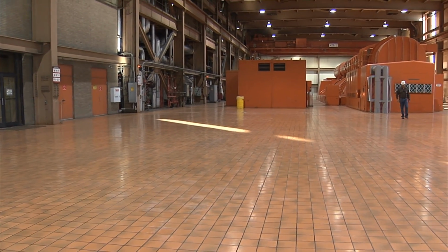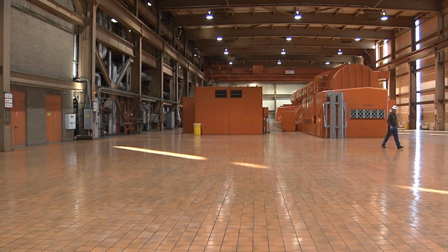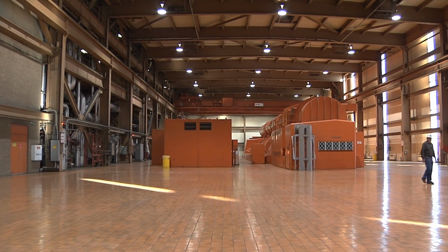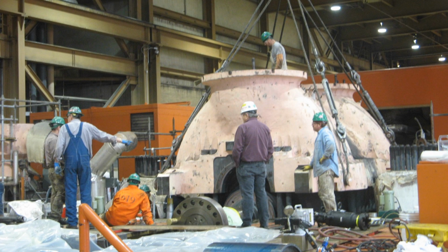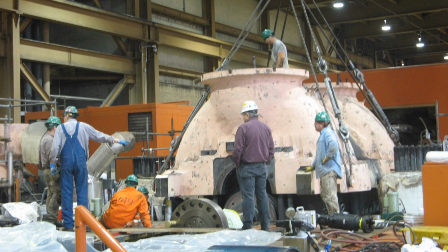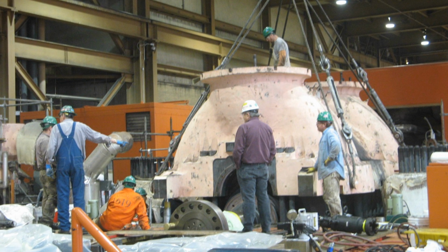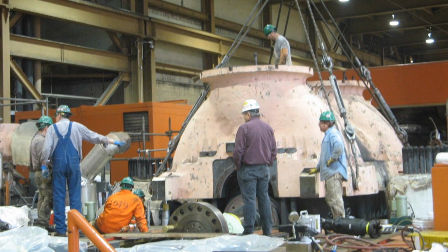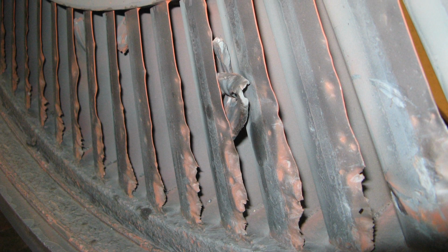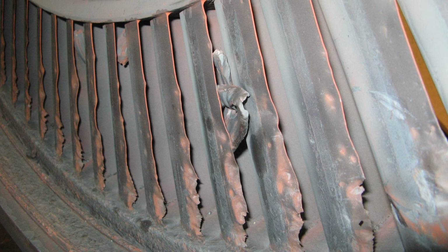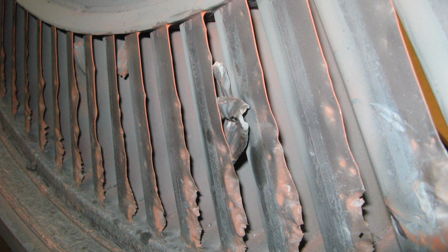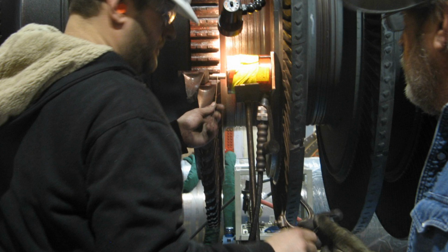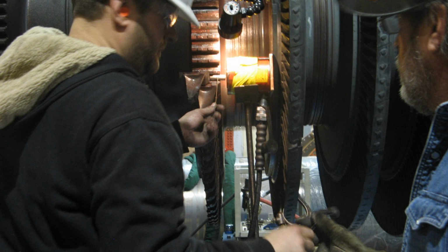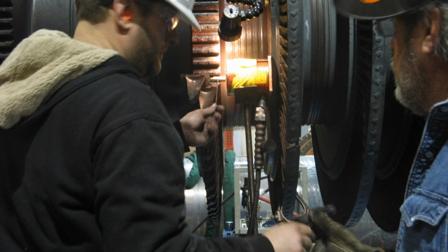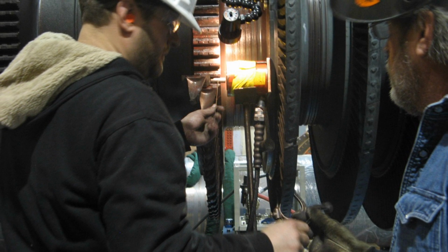During the Unit 2 outage, an inspection revealed that IP turbine bucket covers had lifted and become detached on the IP turbine inlet stage. The IP turbine outer and inner shells had to be removed, revealing that the bucket covers had angel-winged, lifted, and become detached on the turbine end of the 8th stage. The 9th and 10th stage bucket covers had also shown signs of solid particle erosion, SPE, which had eroded the underside and lifted the covers, but they hadn't become detached. The cause of the SPE is coming from the boiler reheat section due to long-term heat damage, which is an industry problem with older boilers.